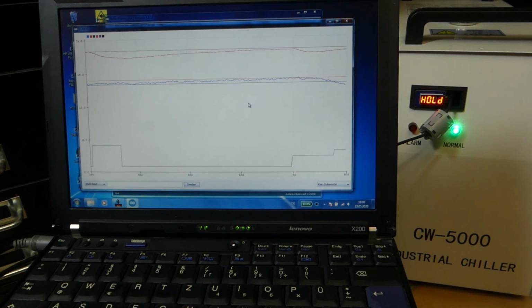So this is the hold. This is when it runs the compressor but has the bypass valve open, just in case it has a very large load. And it's now going to reach the hysteresis point under the set temperature, and it's going to turn off the cooling. And it's going to keep the fan running for exactly 1 minute now. And once the fan has stopped, it is going to go in idle mode, but it is going to keep watching the case temperature.